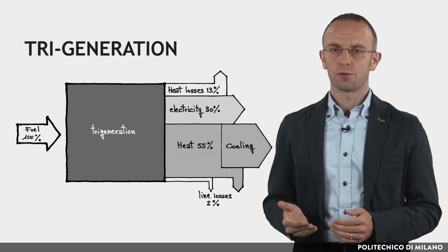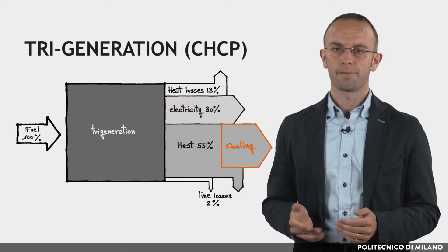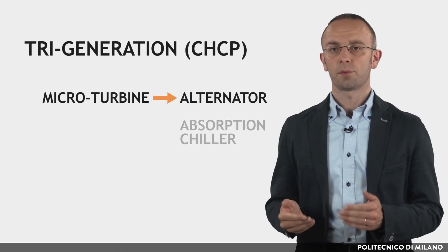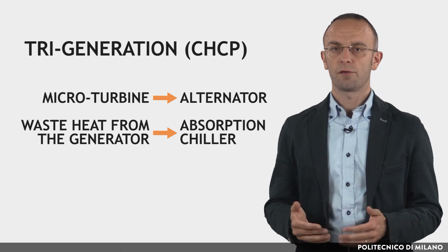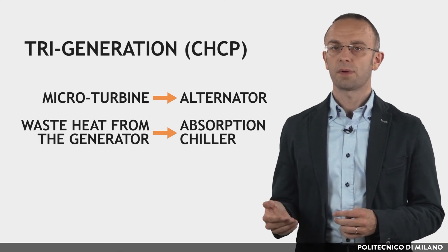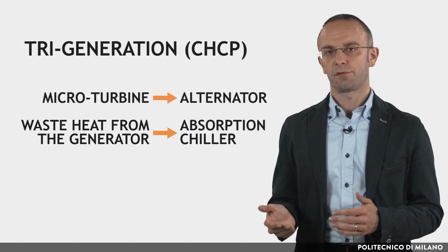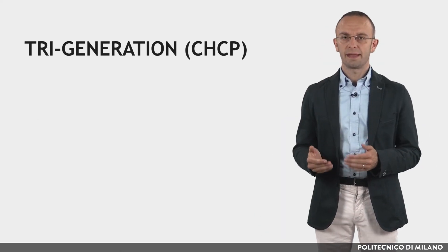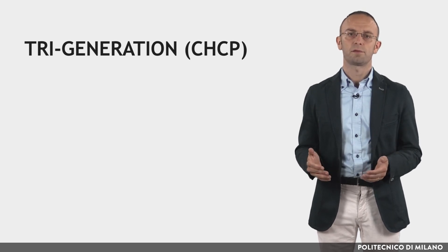With regard to tri-generation, or combined heat, cooling, and power, it refers to the simultaneous generation of electricity, heating, and cooling. The most common technical configuration is made up of a reciprocating engine or a micro-turbine powering an alternator, and an absorption chiller powered by the waste heat from the generator. This system is interesting where there is a constant need for thermal energy — for cooling and for producing domestic hot water — and where availability of electricity from the grid is not always guaranteed. If correctly designed, it can be more efficient in terms of primary energy needs than an air-cooled electric heat pump powered by the grid. The lower the efficiency of the national electricity generation, the more tri-generation systems should be considered in preference to electric chillers.